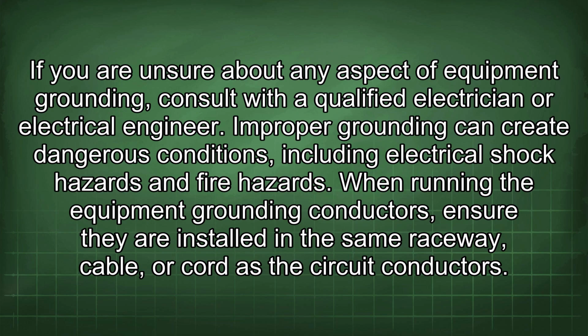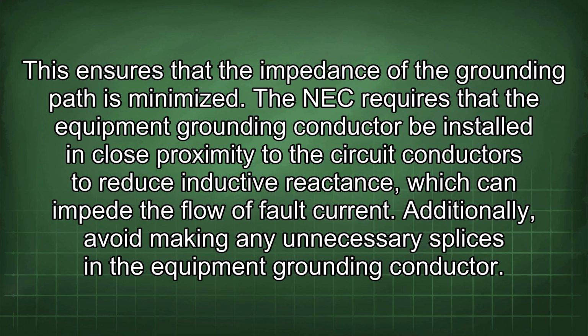When running the equipment grounding conductors, ensure they are installed in the same raceway, cable, or cord as the circuit conductors. This ensures that the impedance of the grounding path is minimized. The NEC requires that the equipment grounding conductor be installed in close proximity to the circuit conductors to reduce inductive reactance, which can impede the flow of fault current.